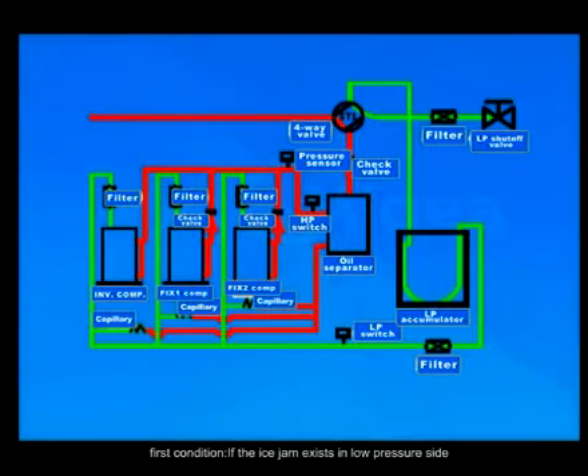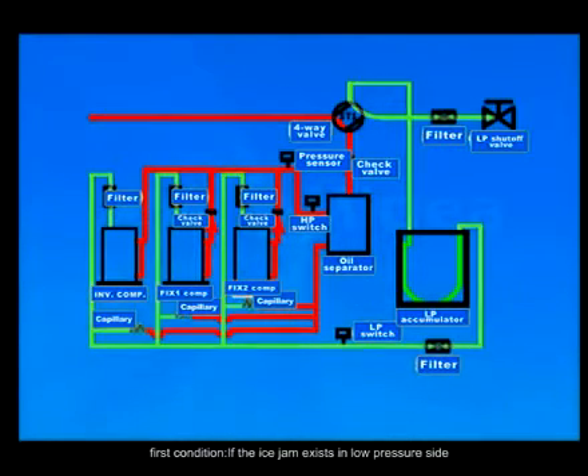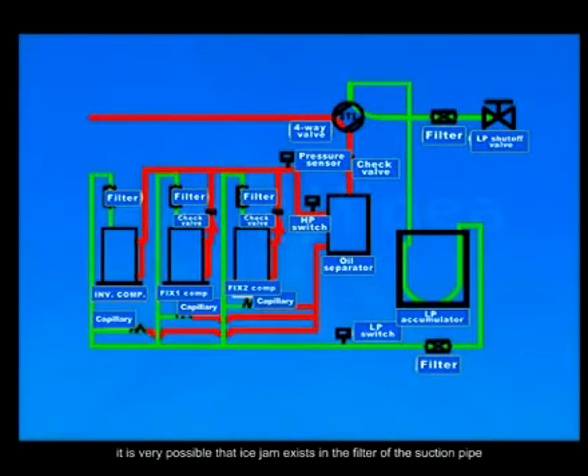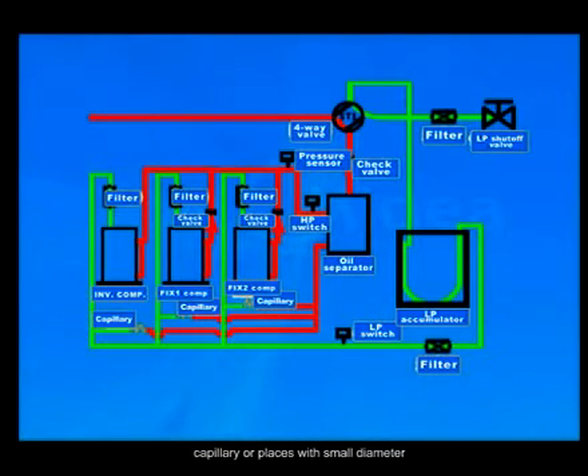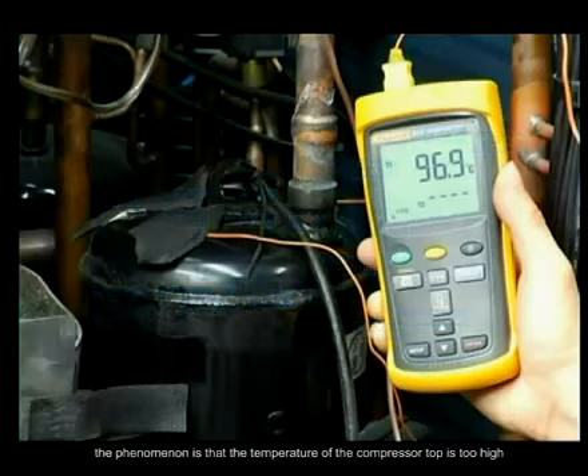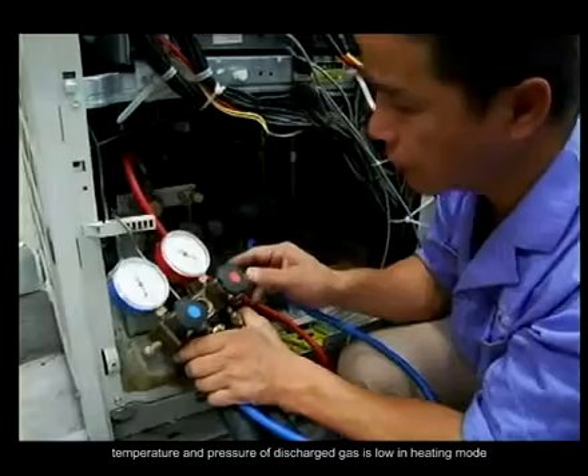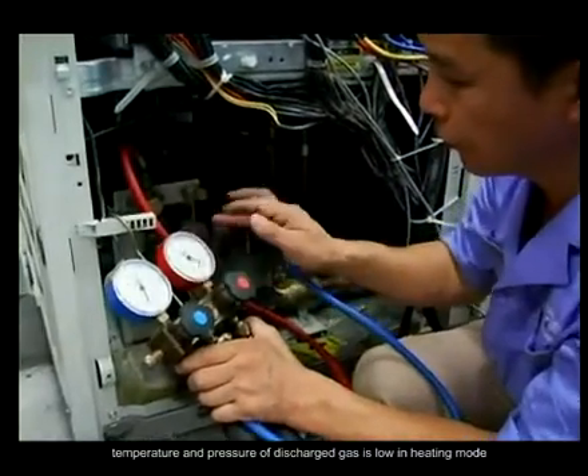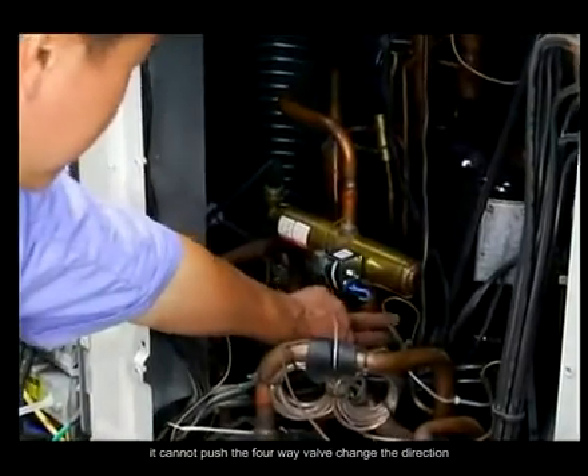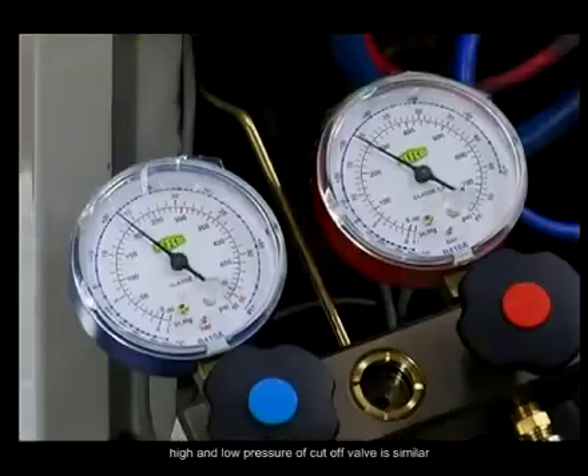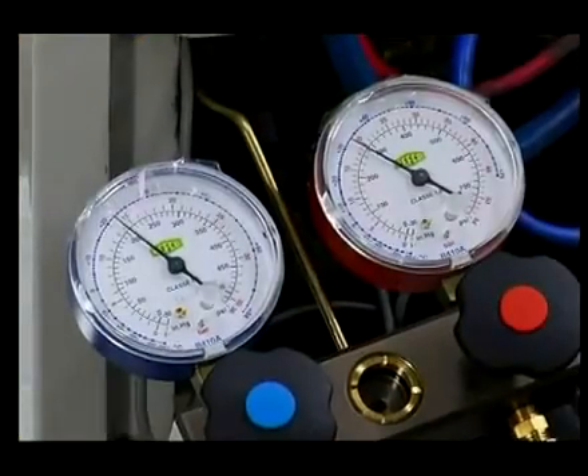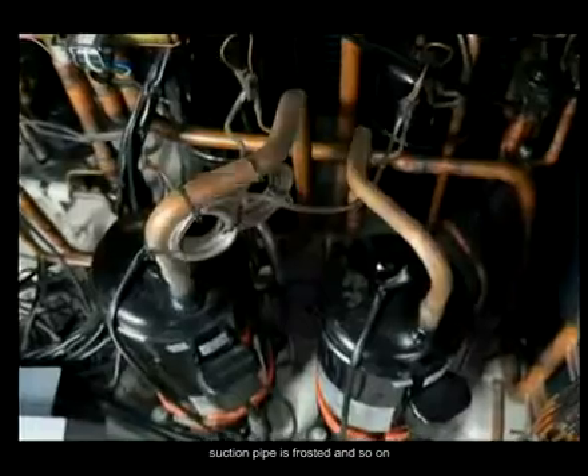First condition. If an ice jam exists in the low pressure side, it is very possible that the ice jam exists in the filter of the suction pipe, the capillary, or places with small diameter. The phenomenon is that the temperature of the compressor top is too high. Temperature and pressure of discharged gas is low. In heating mode, it cannot push the four-way valve to change direction. High and low pressure of the cutoff valve is similar. The suction pipe is frosted, and so on.